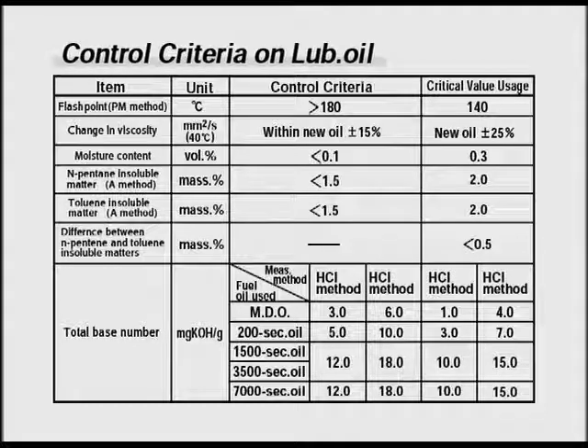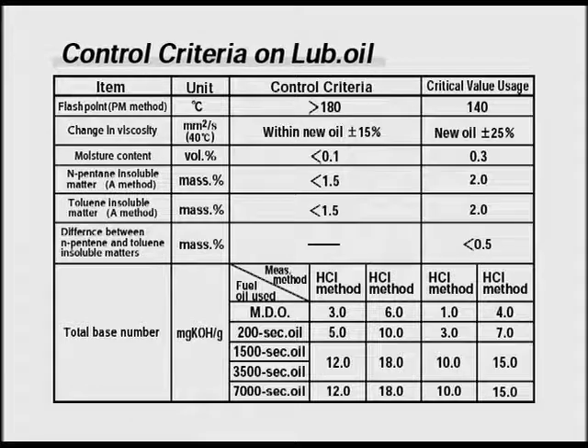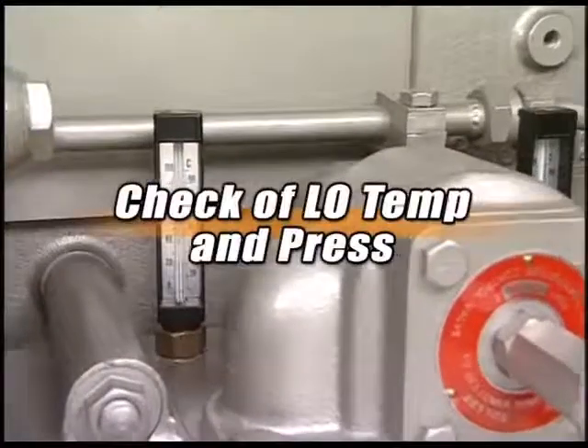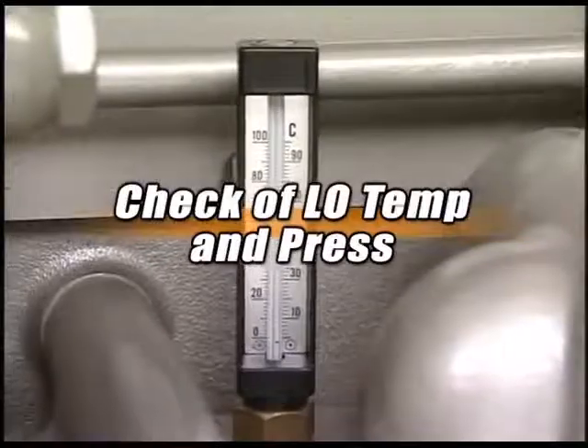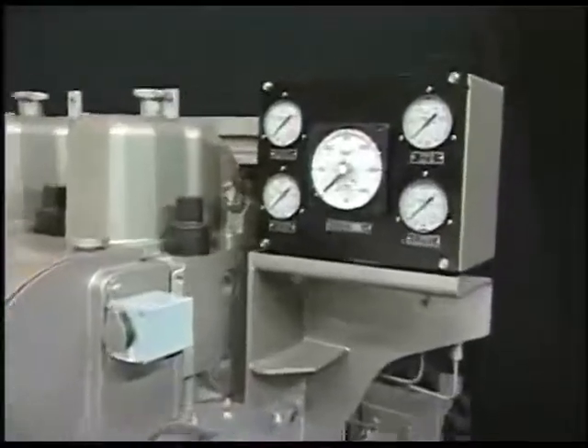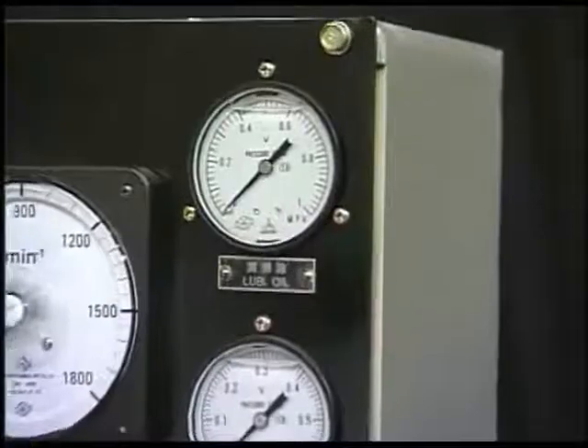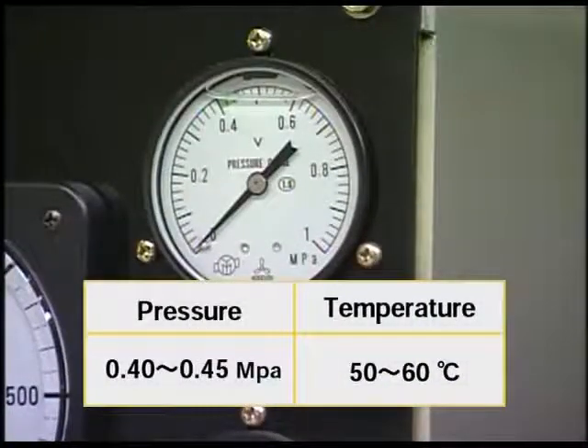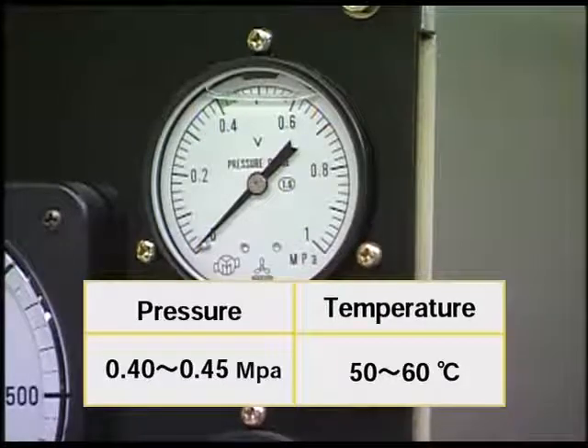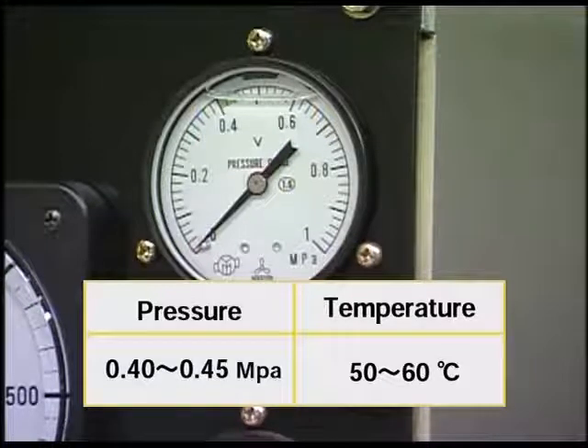Analyze the lube oil properties after every 500 hours of engine operation and exchange the lube oil based on the table. During engine operation, check that the lube oil temperature and pressure are within the specified values. If they are out of specified value, find the cause and take appropriate measures.